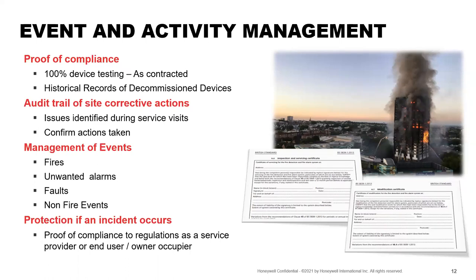So you'd get fire, unwanted alarms, not necessarily false alarms, but unwanted alarms. When somebody burns the toast in a student accommodation, for example, and the detector goes off because there's smoke, that's not a false alarm because the detector's done exactly what it should. It's detected smoke and it's gone off. It's not a false alarm. It's an unwanted alarm. But on the basis that it might be real, the fire and rescue service respond.